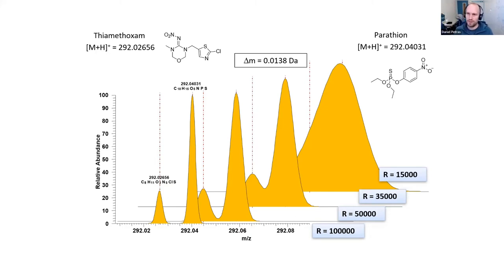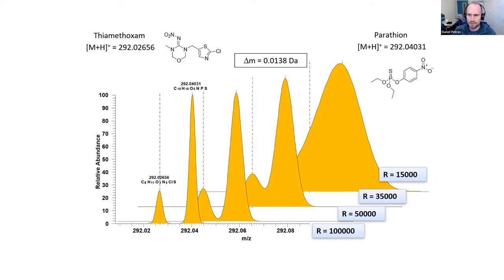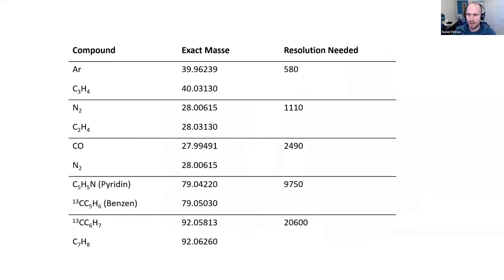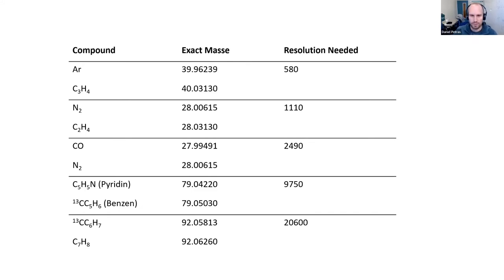Mass specs are often considered just as lines with a very specific mass, but actually you typically have Gaussian distributions when you measure them in profile mode — where you have all the raw information. This is really important to consider when thinking about what type of mass spec to use. Here are some examples of what resolutions would be needed to separate certain very close masses: there are many elemental compositions that yield almost isobaric conditions, and high resolution is typically the way to go.